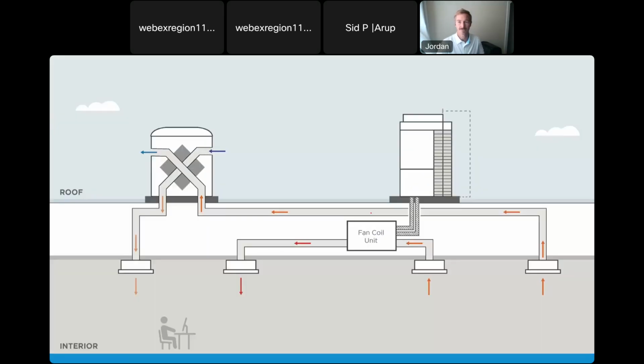Quick schematic. When I talk about DOAS and very high efficiency DOAS, we're talking about an entire system. So not just the ventilation unit, we're talking about kind of 4 key concepts that make a DOAS system very high efficiency. One is a fully decoupled system. So we have equipment or a few pieces of equipment that are dedicated to providing ventilation air, and they do so typically directly to the building.